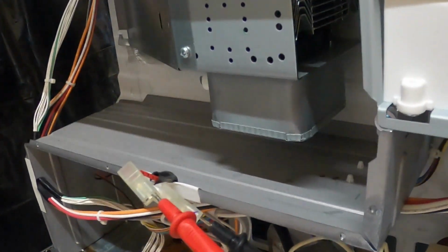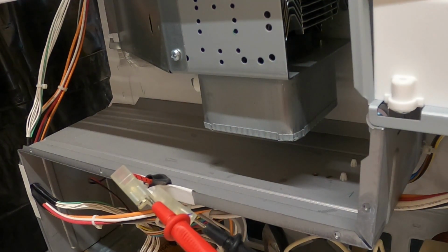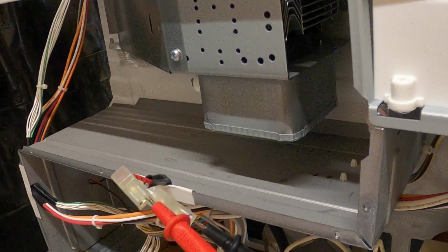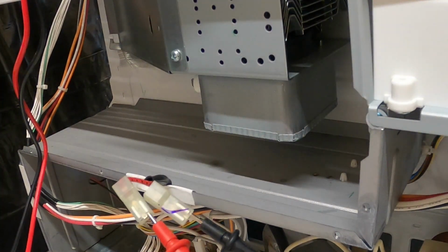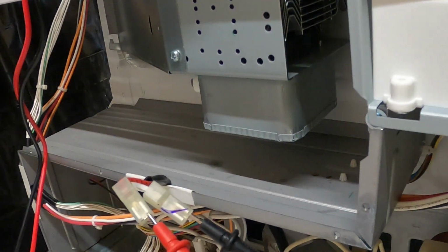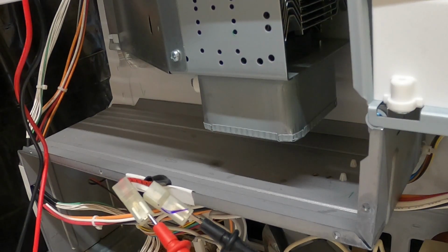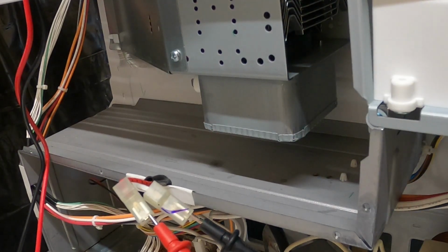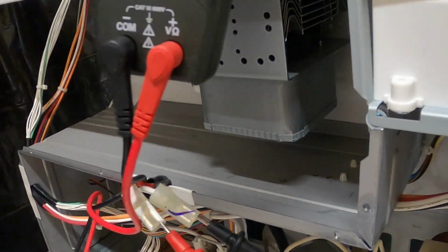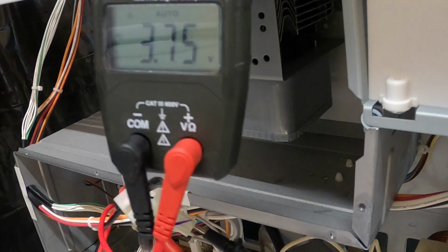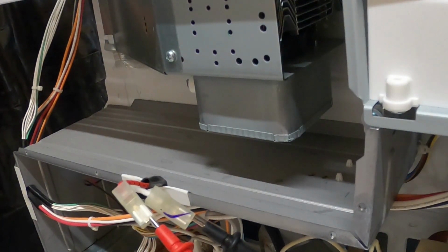But anyway, what we're doing now is we're checking for that 3 volts AC filament voltage. To review, high voltage leads disconnected. You've got your meter leads in, and you're looking for 3 volts AC. So we're going to come up here, start. And you'll notice we have 3.75 volts. So we have filament voltage. That tells you that the filament side of your transformer is good.